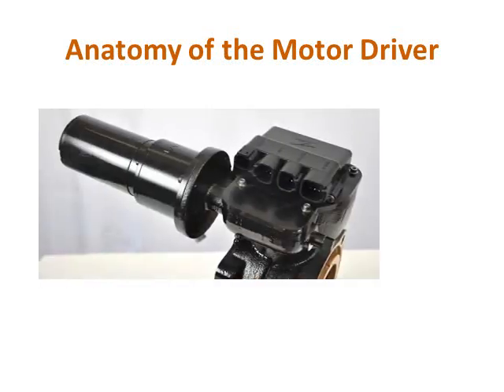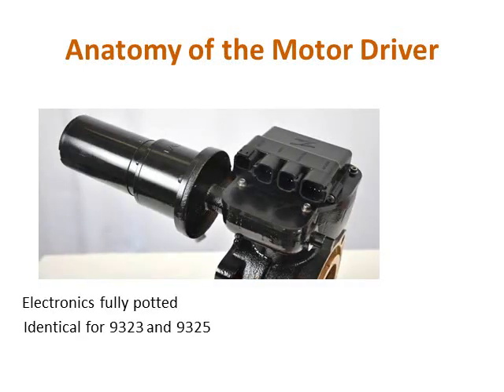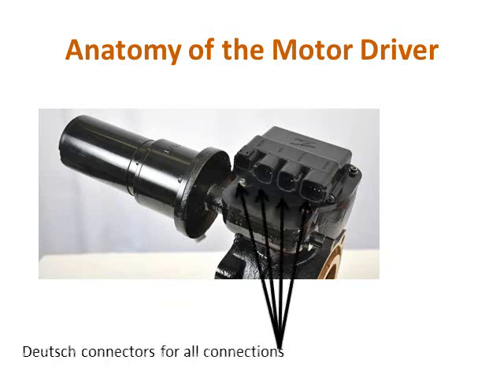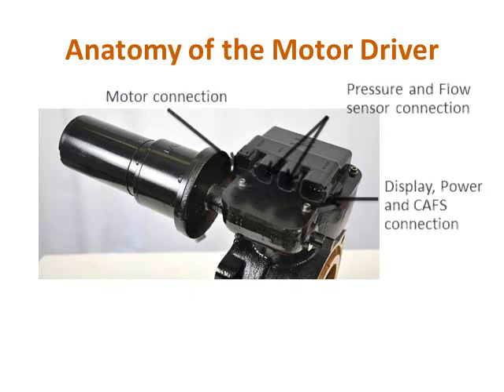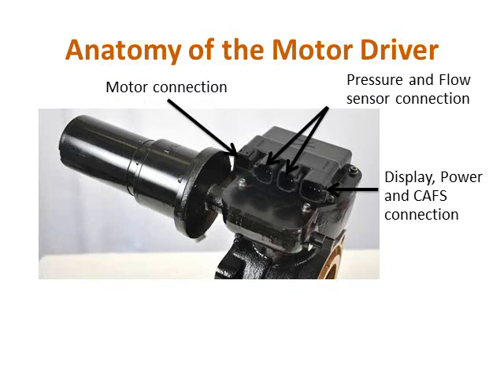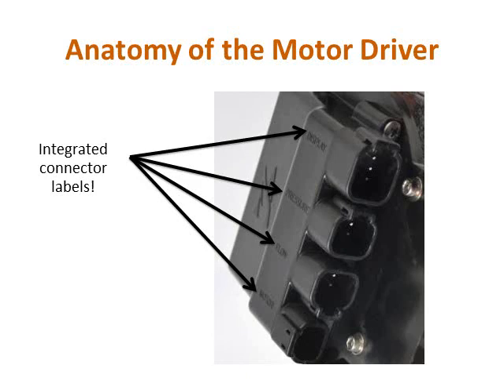The motor driver is fully potted, making it impervious to shock, vibration, and moisture, and it is identical for both the 9323 and the 9325 Navigator Pro displays. The motor driver also has integrated Deutsch connectors. All of the system devices are connected directly to the motor driver. It is no longer necessary to run the pressure, flow, motor, or CAFS wires back to the pump panel. And to make sure the pressure and flow sensors are connected properly, the Deutsch connectors are keyed, so they only accept the proper mating connector. To make installation and service as easy as possible, the connector labels have been molded into the top of the motor driver.